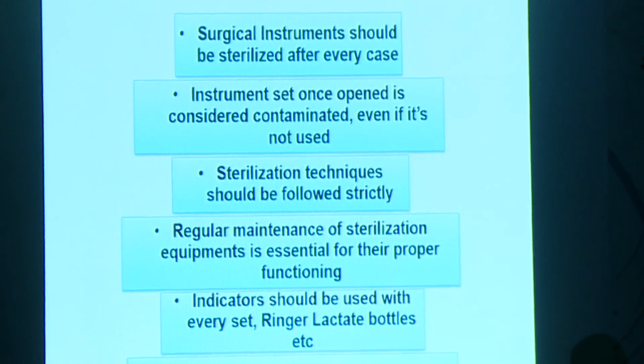So sterilization, surgical instruments should be sterilized after every use, every case. Instruments once opened are considered contaminated, whether used or not. Sterilization techniques should be followed strictly. Each and every step should be meticulously followed. Regular maintenance of sterilization equipments is essential for their proper functioning. Indicators should be used with every set, and documentation of each and every step with date and signature is a must.